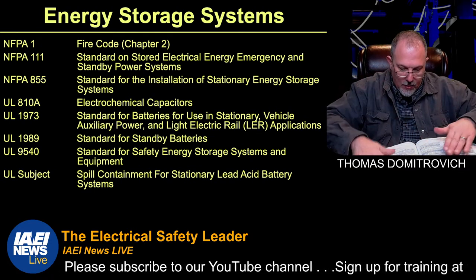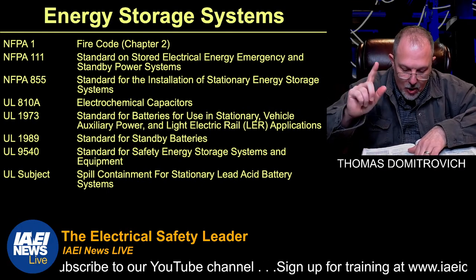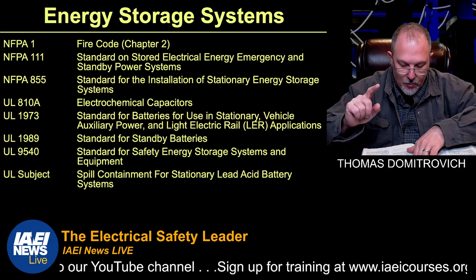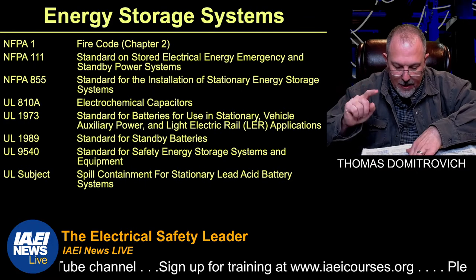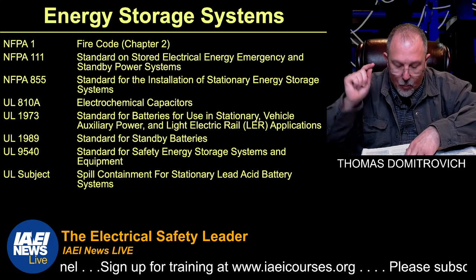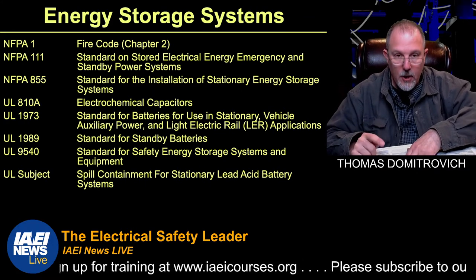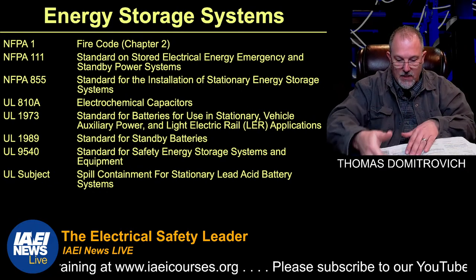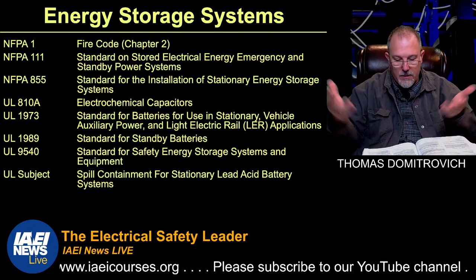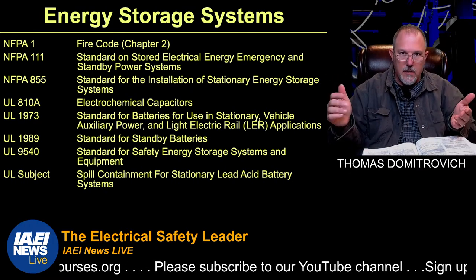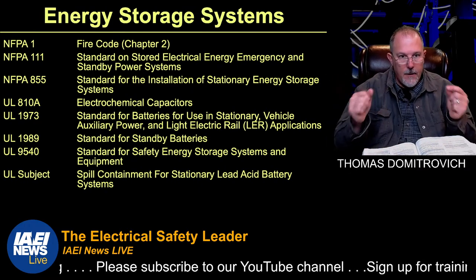In the 2020 code, they said that 706 only applies when the energy storage system has a capacity greater than 3.6 megajoules or 1 kilowatt hour. So now they've limited the application of 706 to a little bit larger systems - anything greater than those numbers.